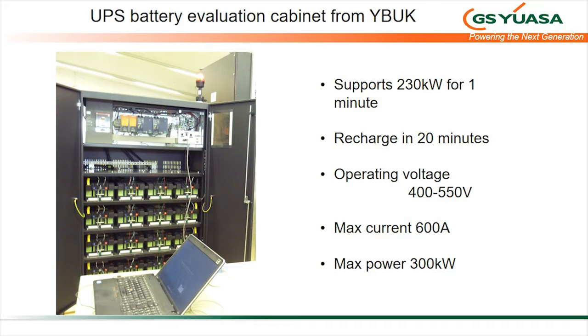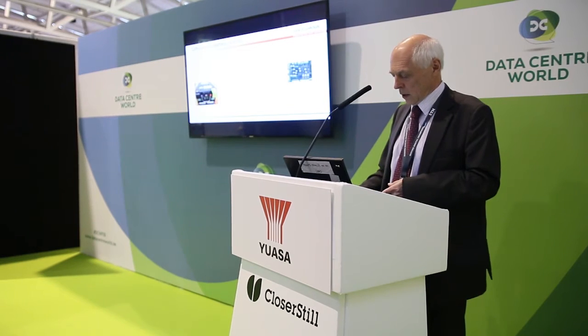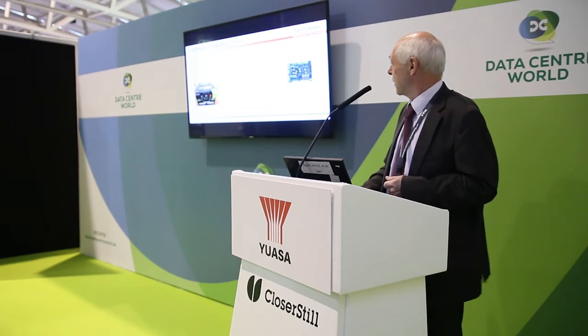So you're talking about 230 kilowatts over a 1 minute discharge in a relatively very small cabinet. And the max power for 10 or 15 seconds could be something like 300 kilowatts in that footprint. I won't go too much into that. That's just a circuit diagram which you won't see anyway, so I'll skip over that.